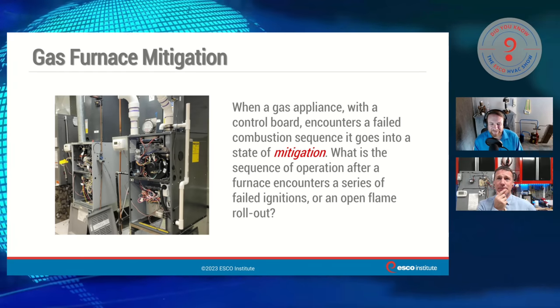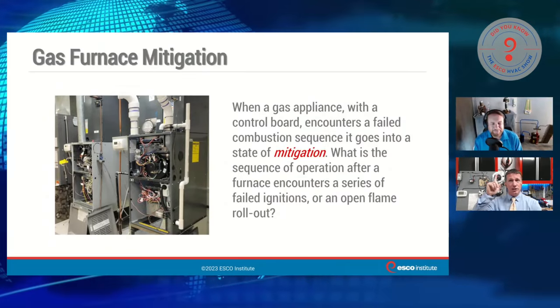If we have a furnace in our ignition process and it doesn't light, it didn't just simply spray gas out. We first have a safety control that says hey, there's not a flame where it should be. The flame sensor says there's not a flame, and the first thing the control board does is say let's shut the gas valve off.